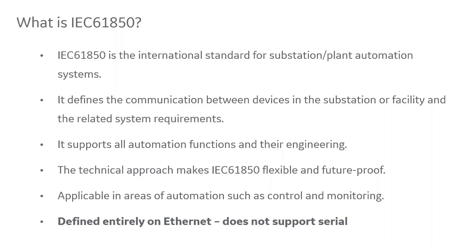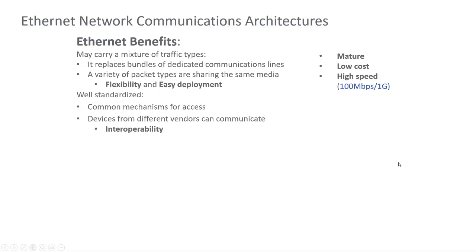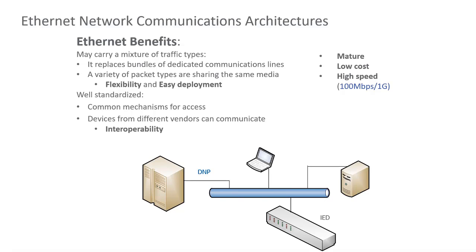One of the ideas behind 61850 is that it's broad, flexible, and future-proof — any applications that come out in the future can be fit into the IEC 61850 model. It is defined entirely on Ethernet and does not support serial. Because of that, Ethernet communication becomes an integral part of what we need to understand before diving into 61850.